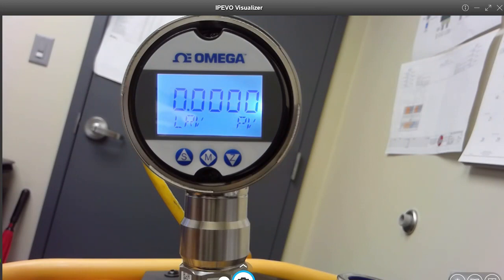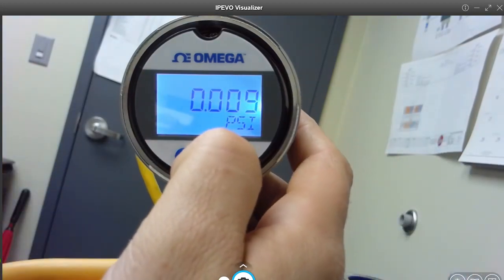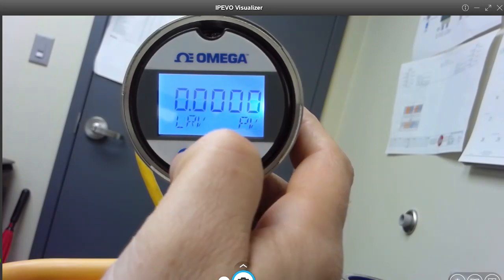Next, we're going to have to edit this one because these have quite a range. They will do absolute 0, which is negative 14.5 to 1000 PSI. We want better resolution, and our units will fault above 550. So we're going to set ours into the normal range of what we could expect to see from a unit. So in order to do this, we're going to have to modify this value. So we're going to hit menu. We're going to get back there.